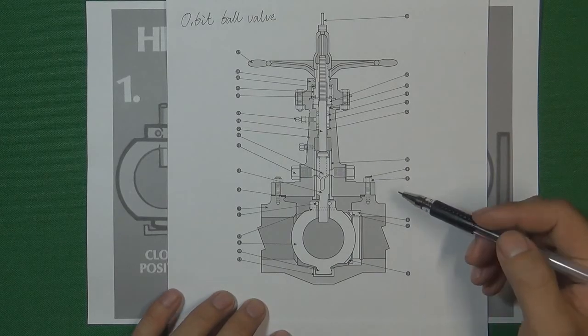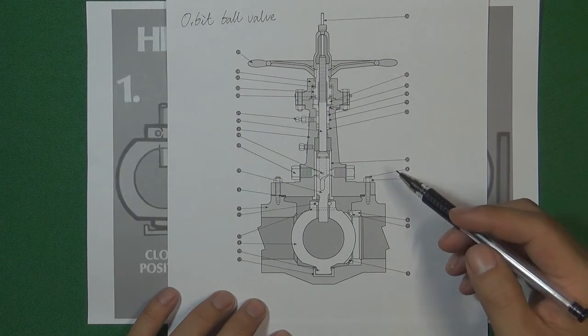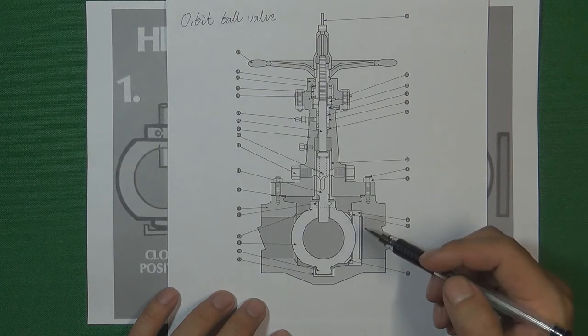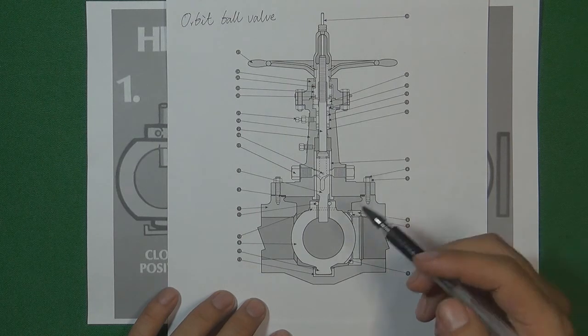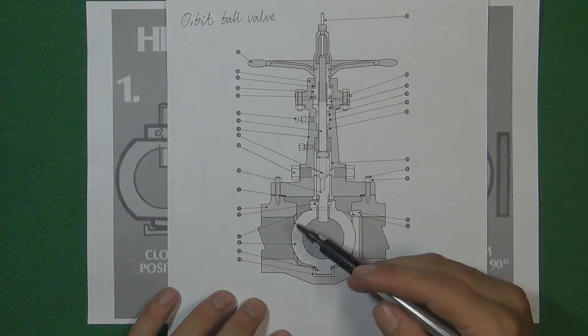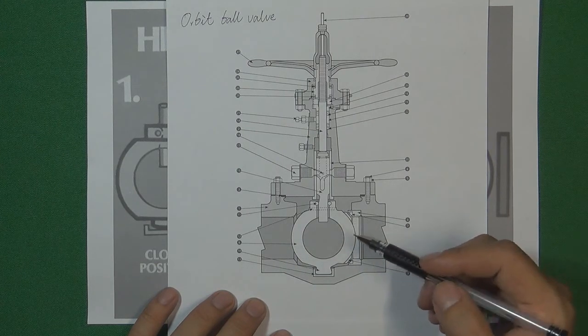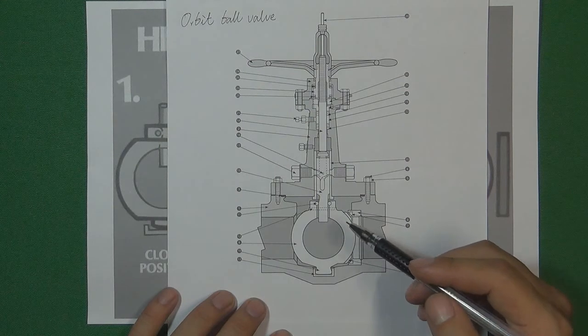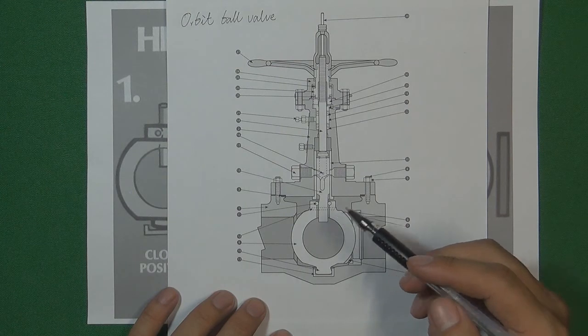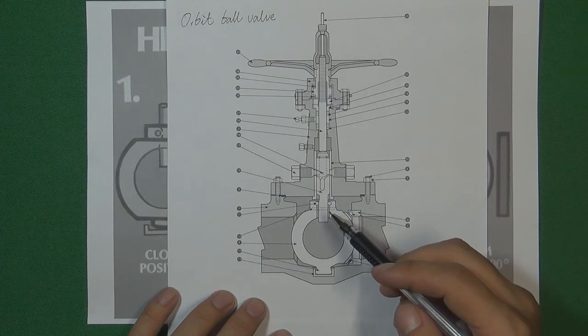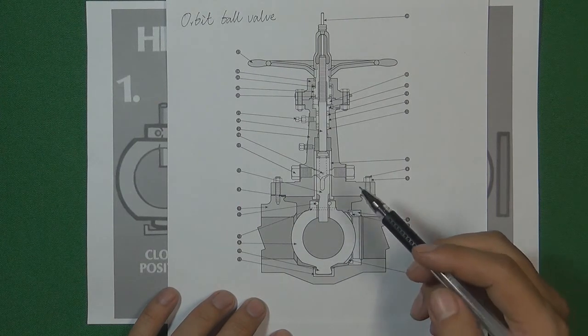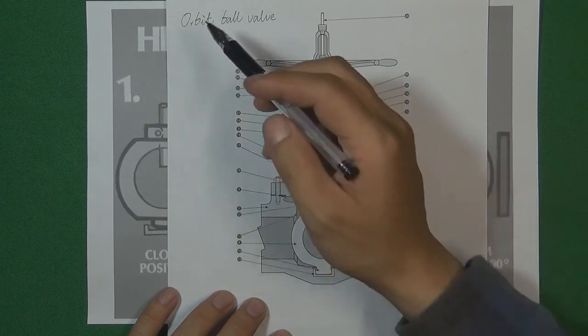The next one is a very special ball valve. We want to design a ball valve where, when we open it, the ball will not continue to touch the valve seat, and also the ball valve can work in high temperature and high pressure environments. So first we must use a round ball to design the ball, because the round ball's mechanical strength is much better than the half ball. Then we divide the ball movement into two parts: one is the ball leaving the valve seat first, and then turning. So engineers designed this kind of ball valve, which is called an orbit ball valve.